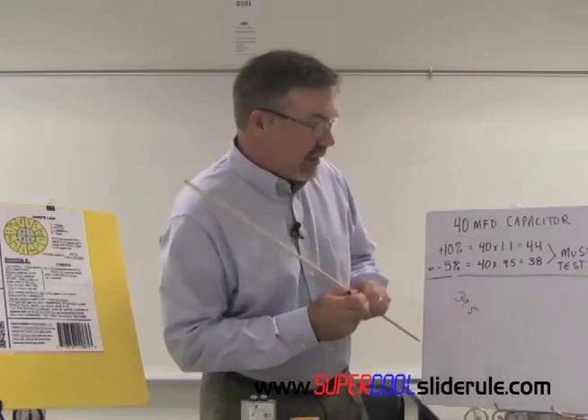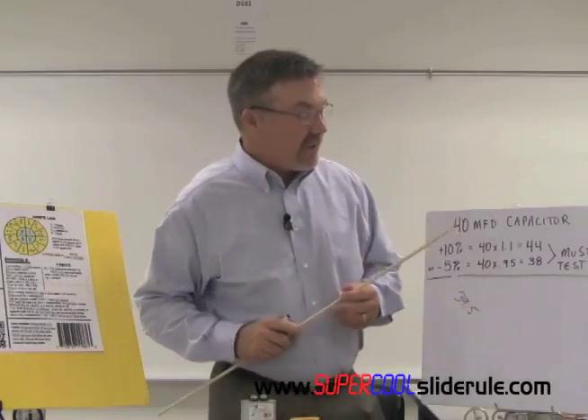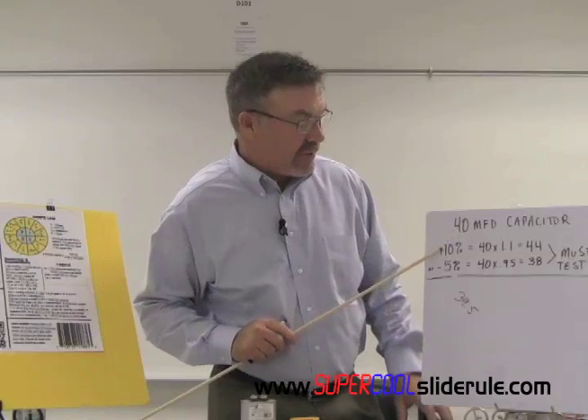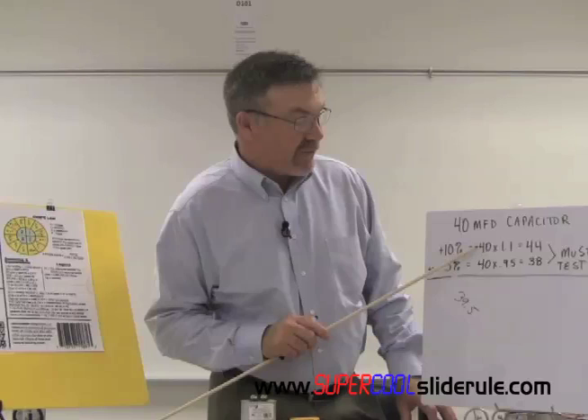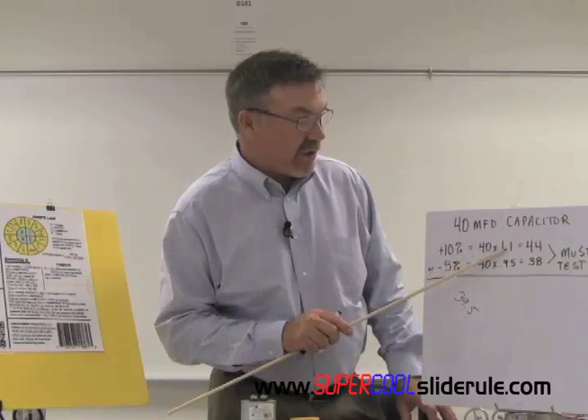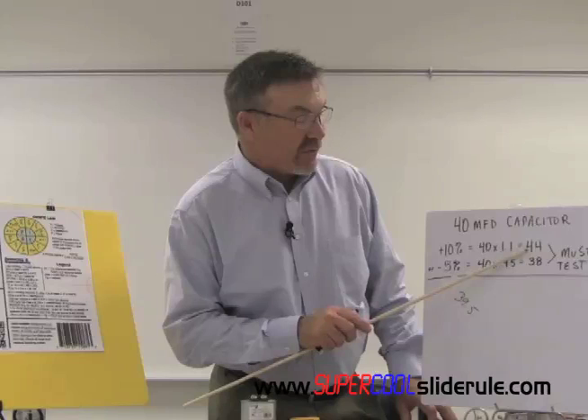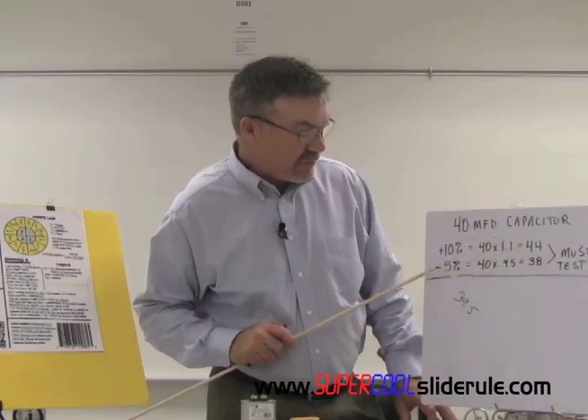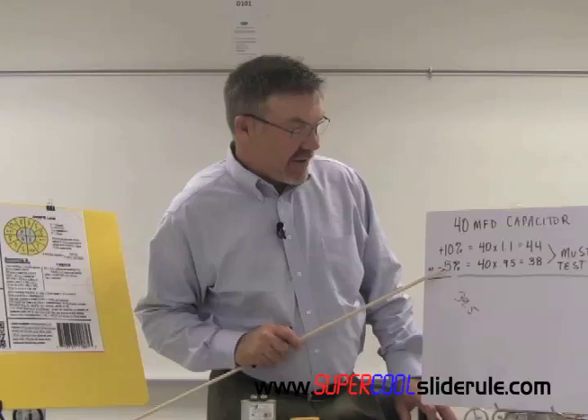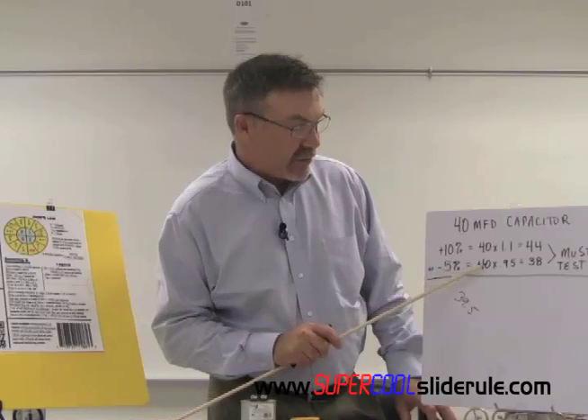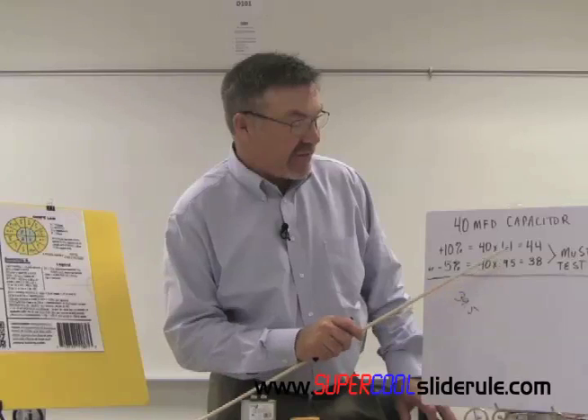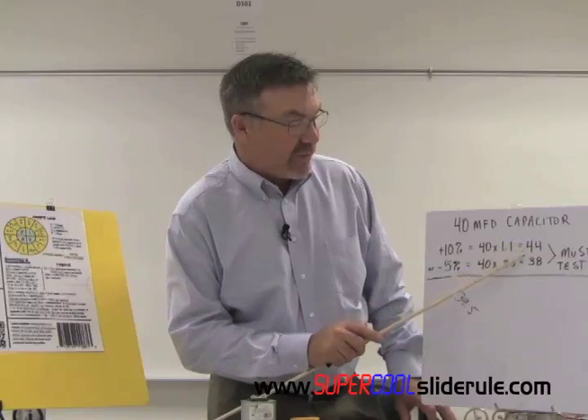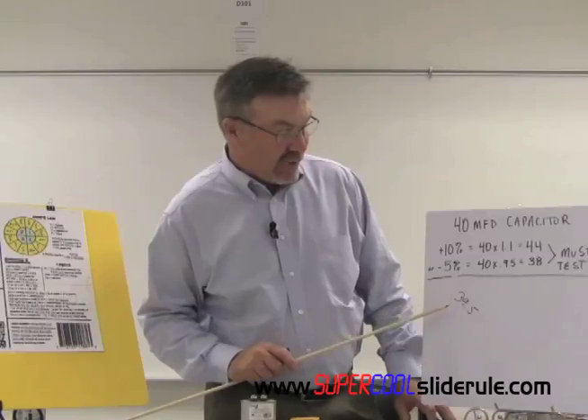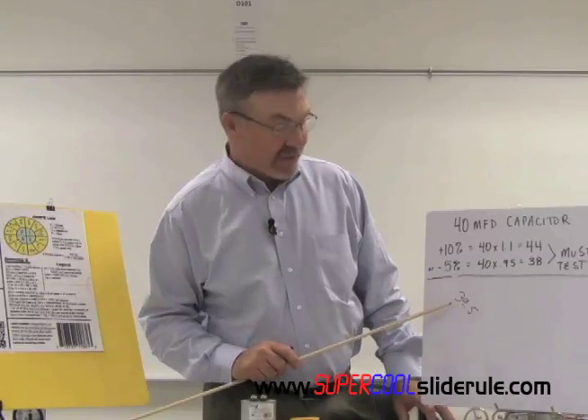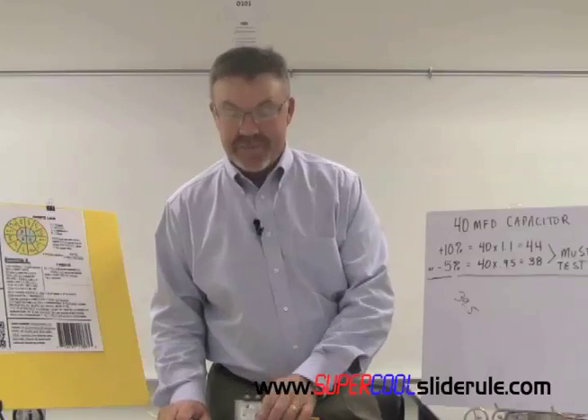39.5. Now, a 40 microfarad capacitor, 10% over, all you do is multiply your 40 by 1.1 to represent your 10%. So 44 on the high side. 5% on the low side, we are looking at multiplying 40 by 0.95. So we must be between 44 and 38. Now we had a reading of 39.5, so this capacitor is good.